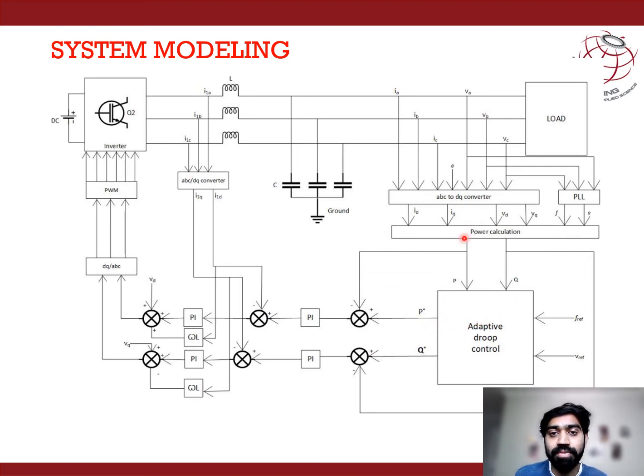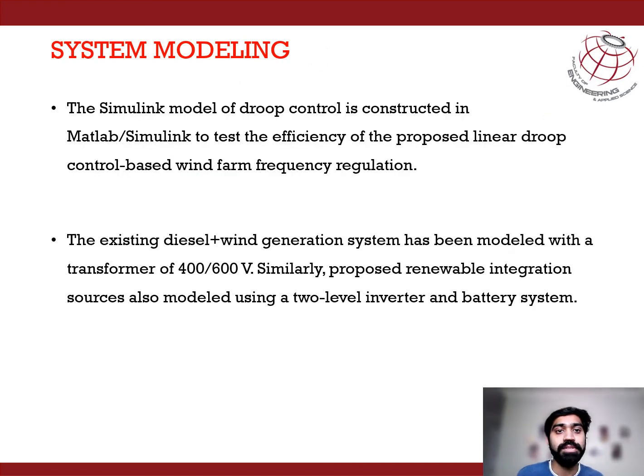Now the active and reactive power of the grid side are compared with the reference active and reactive power, which are generated with the adaptive droop control. The difference is the input signal for the power PI controller, and the output of the power PI controller is sent to the current PI controller to supply the gate pulses of this inverter. So this is the basic MATLAB system modeling that we have used to create our MATLAB model.